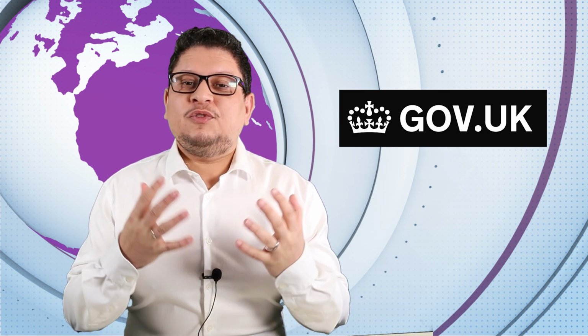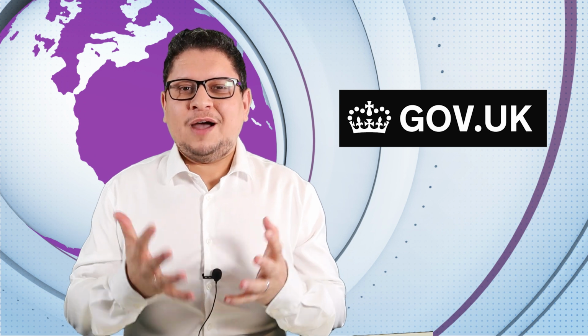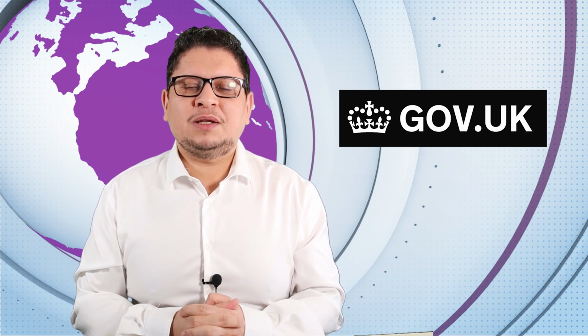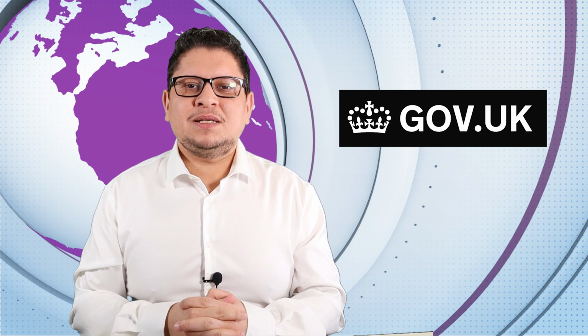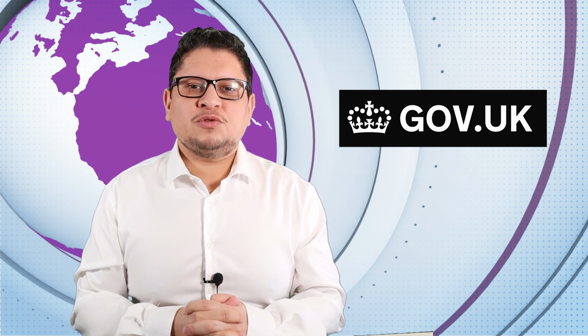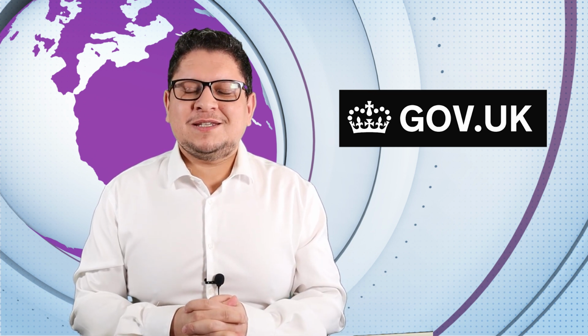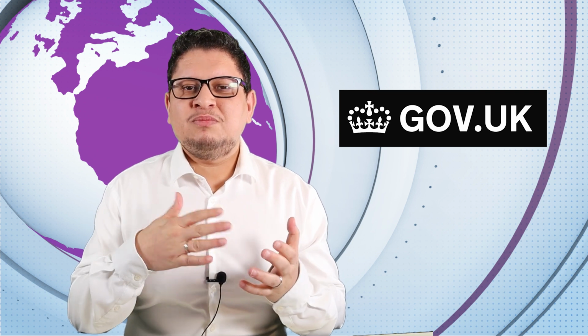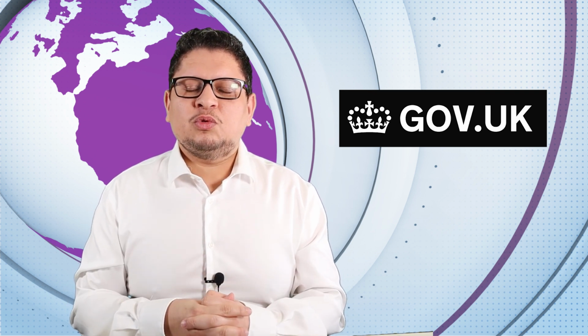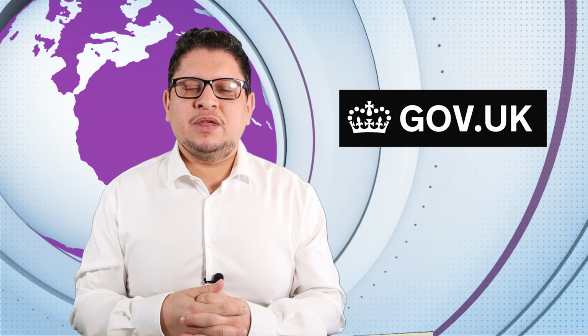So if you are a manufacturer, you can do nothing. You have to ask your UK responsible person to do that for you. So they will go on the MHRA database and they will do this exercise also. So don't be surprised by this message. And it's nice because they are doing that 3 months before. It's not like doing that 1 or 2 weeks before. So it's really a good thing. But it's not a big problem. It's not a big deal. You can do that easily.